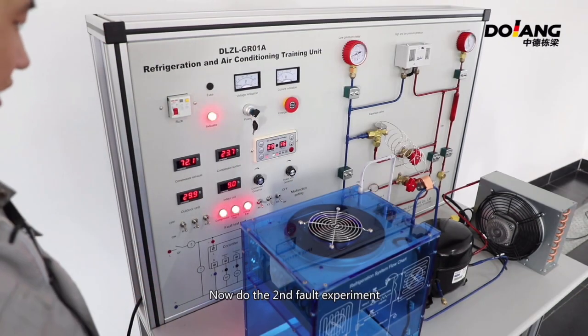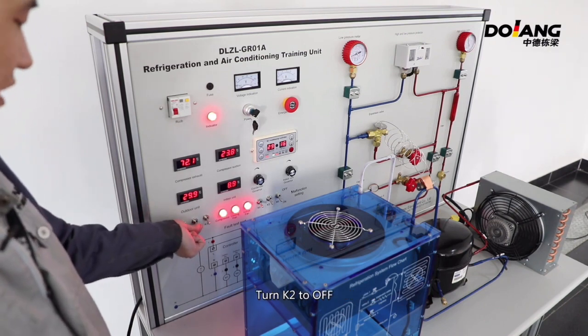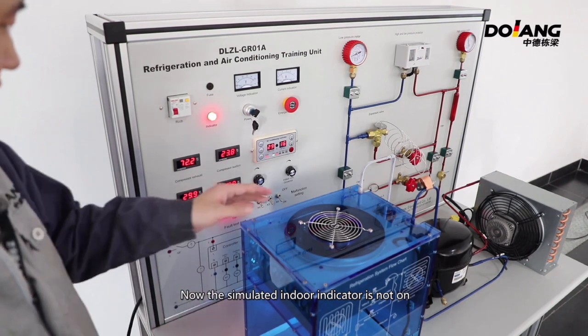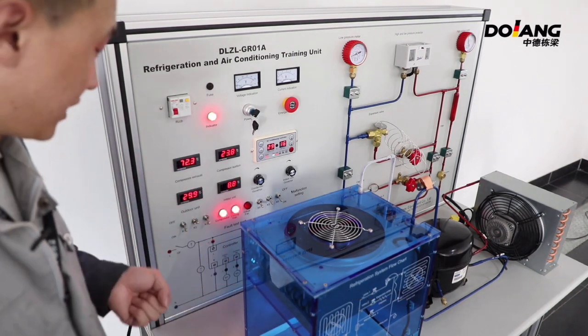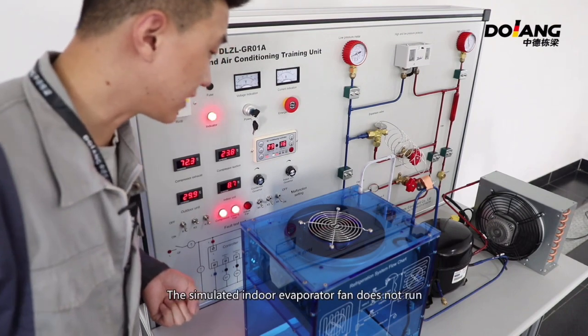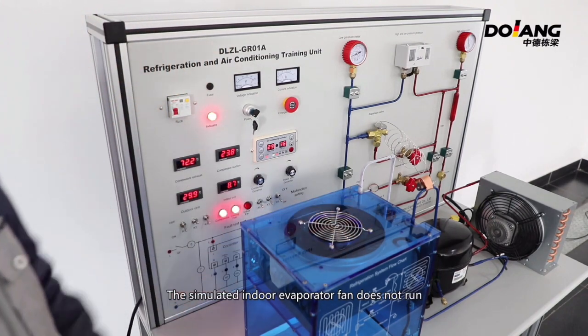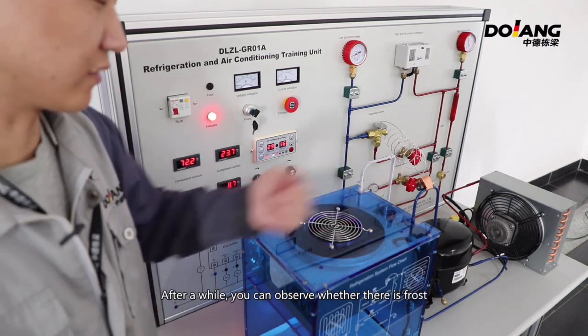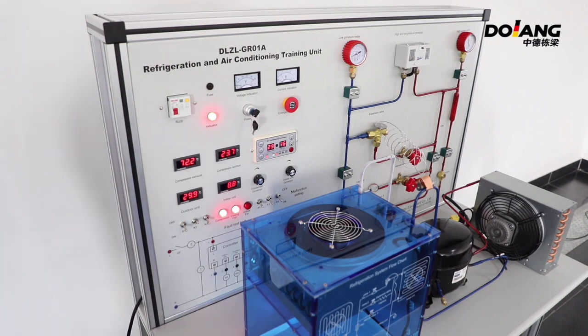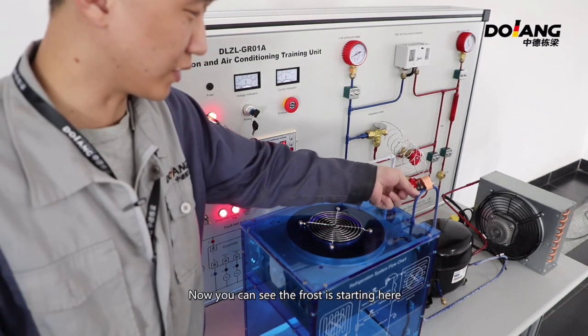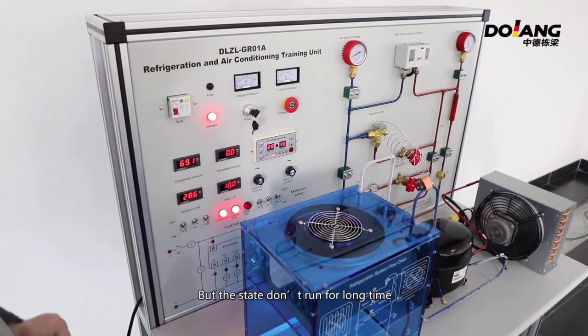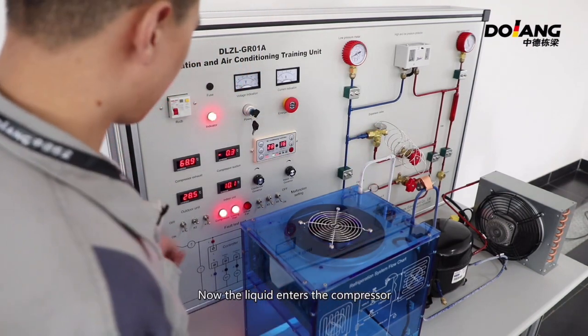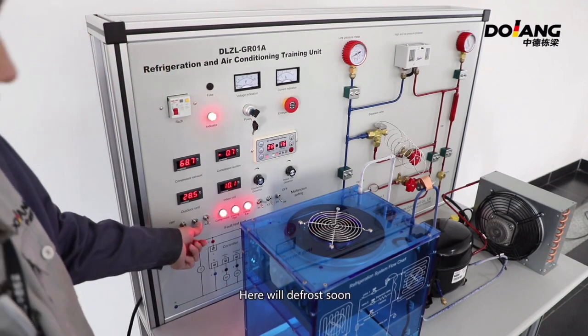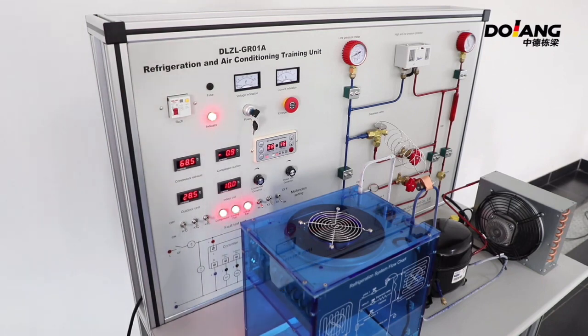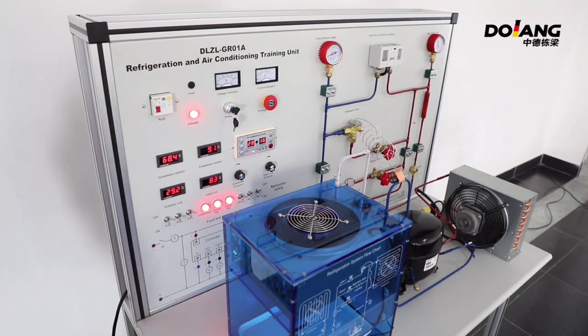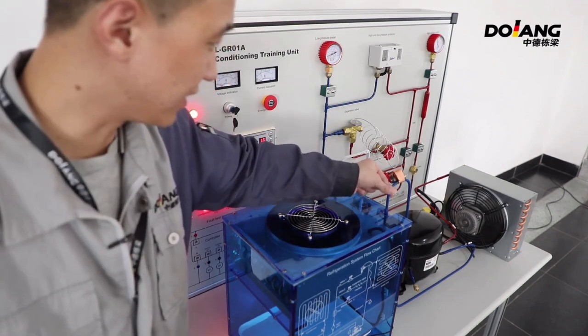Now do the second fault experiment. Turn K2 to off. Now the simulated indoor indicator is on. The simulated indoor evaporator fan does not run. After a while, you can observe whether there is frost. Now you can see the frost is starting here, but the state does run for a long time. Now the liquid enters the compressor. Turn on K2. Here will defrost soon. It's now in no fault status.